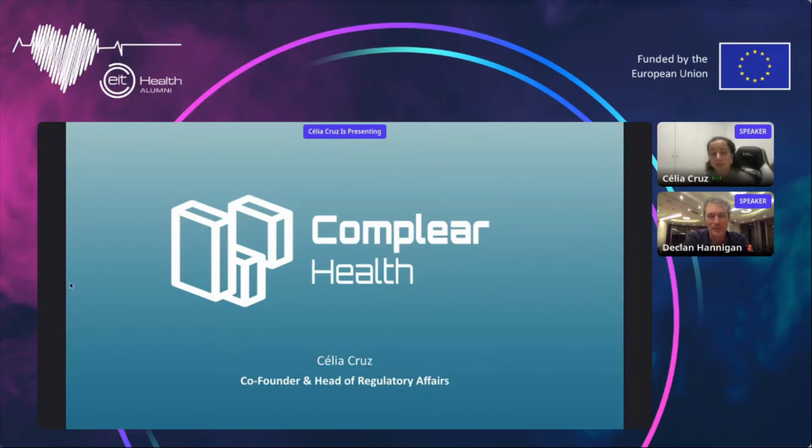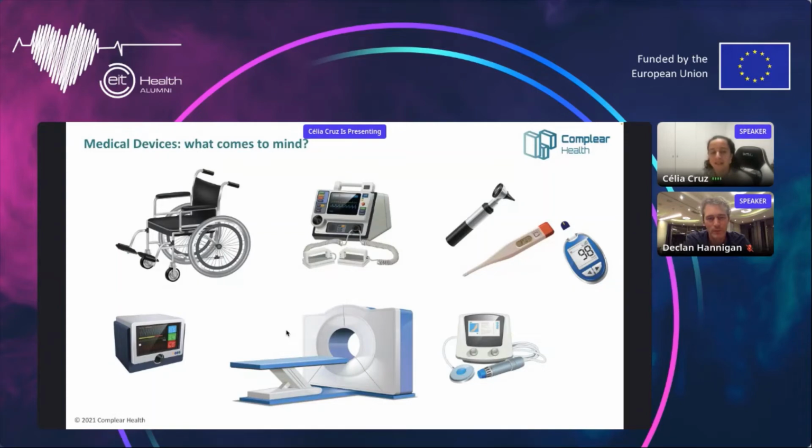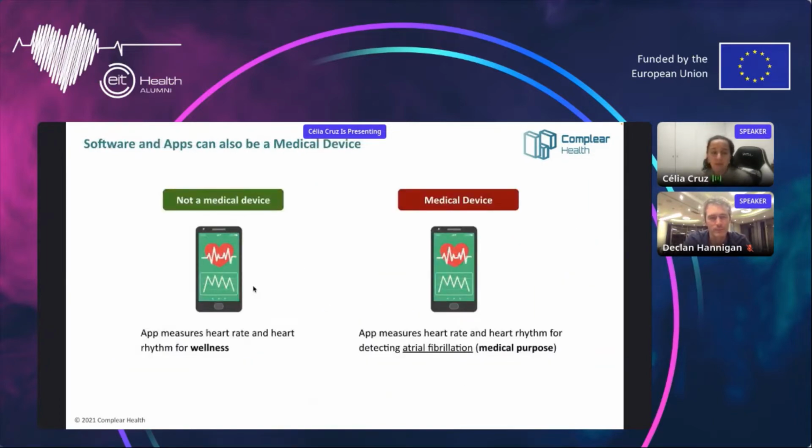So I come here to talk to you a little bit about Complear and some info on regulation of medical devices, and mainly software as medical device. When we typically think of medical devices, we think of the most traditional ones: pacemakers, ultrasound, CT, MRI. But as most of you know, software can also fit as a medical device if it has a medical purpose. In the end, it all comes down to what you intend to do with the software or with the app. And this may be trickier than you think, since you are often in the gray area of regulation, mainly with software.